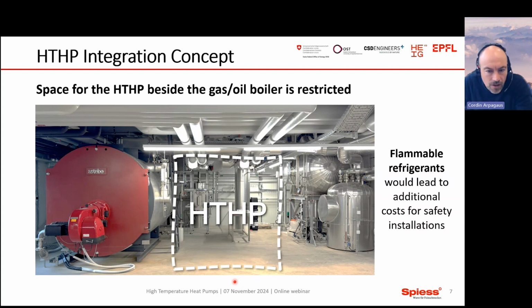Here you see a picture of the installation of the gas boiler, and then the steam storage, and then the steam network, and here space for a possible high temperature heat pump. You see that the space is quite restricted, so they did not consider flammable refrigerants as a possible solution at first sight, because it would increase the costs for safety installations.